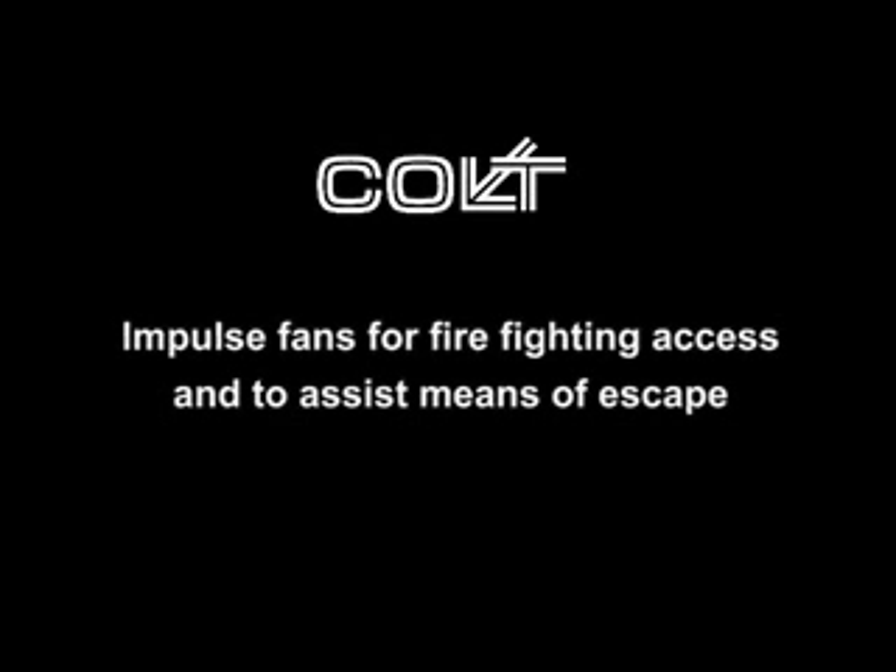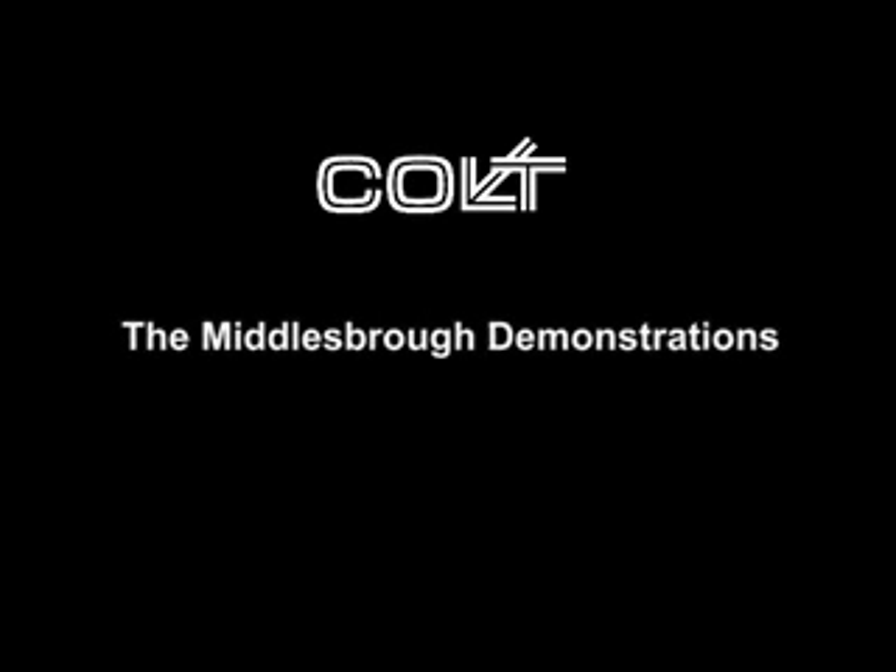Ventilation of basement car parks using impulse or jet fans in conjunction with extract systems is a well-proven method that is commonly used in the UK. In 2004, Colt carried out a series of demonstrations in a car park in Middlesbrough to show that such a system is at least equivalent to the ducted mechanical extract systems detailed in approved document B.